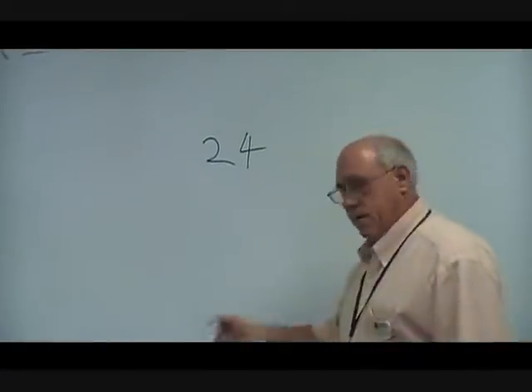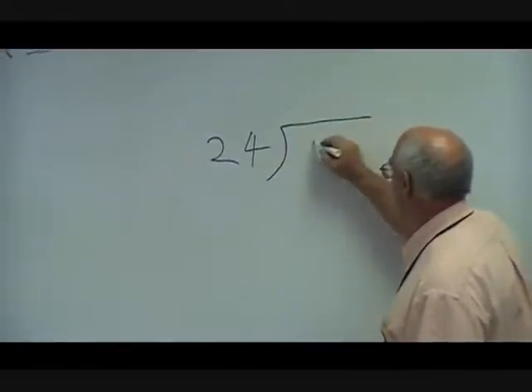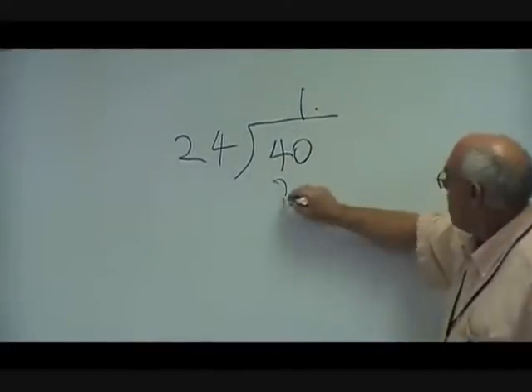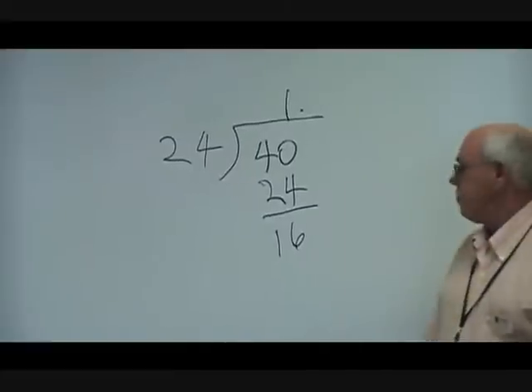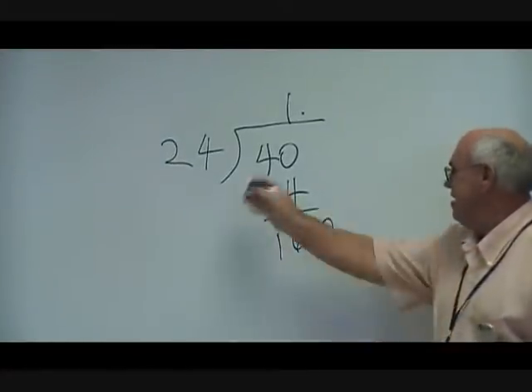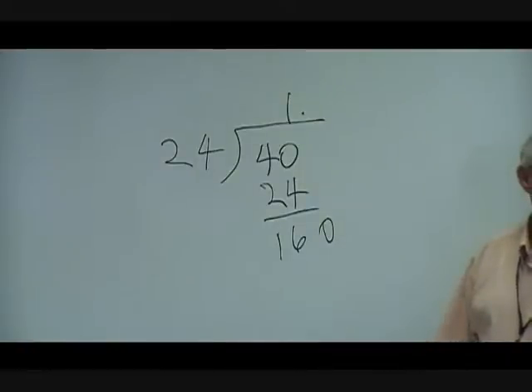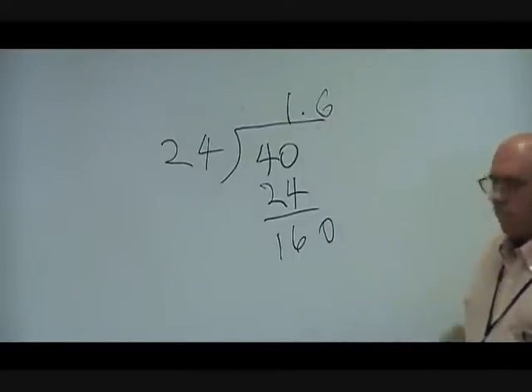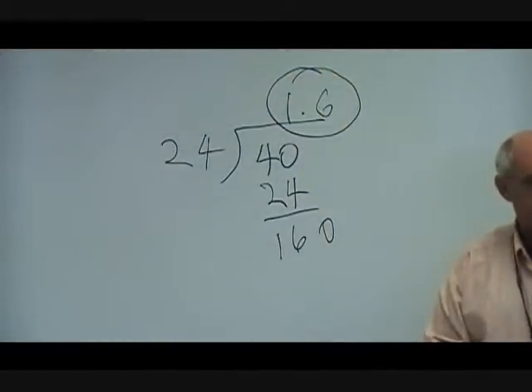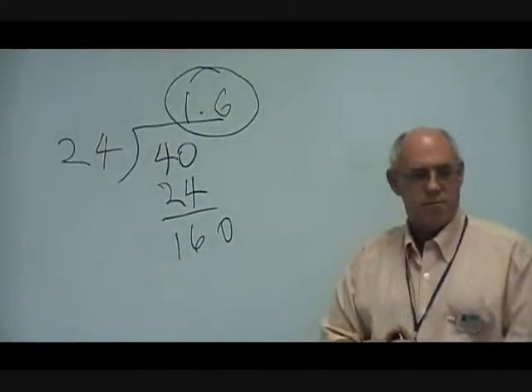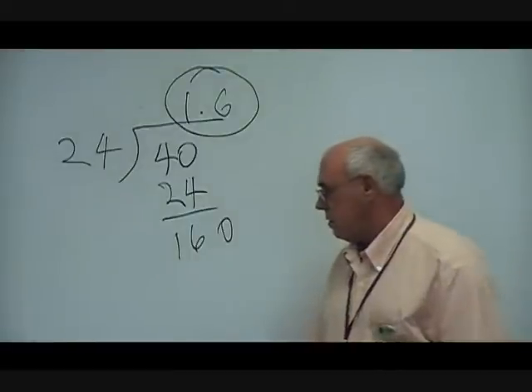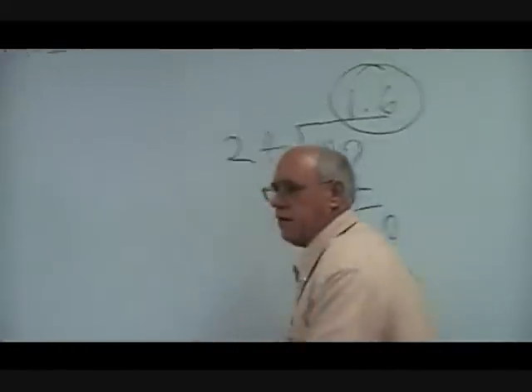If we take the 40 VA — that's our total power — and divide by 24 volts, that goes about 1.6 times. So that tells us the maximum amp draw we're going to get out of that 40 VA transformer is 1.6 amps. If you go past 1.6 amps, you're exceeding the amperage that transformer can produce at 24 volts. That's what the VA rating is about — it tells you the maximum amount of power you can draw from that transformer without overloading it.